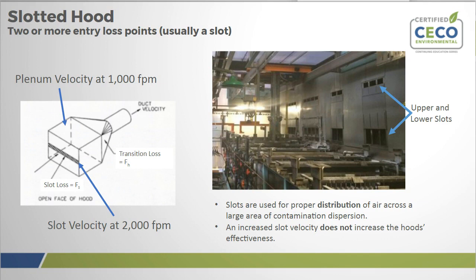Slotted hoods are unique in that they have two points of entry loss. There is a slot coefficient F sub S based on the standard design slot velocity of 2,000 feet per minute. There is also the hood entry loss coefficient, the F sub H, that results from transitioning from that hood plenum to the duct.